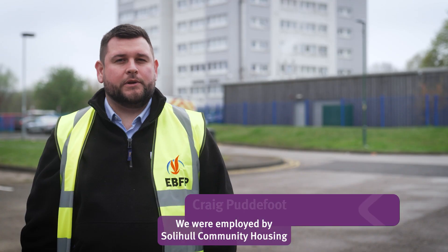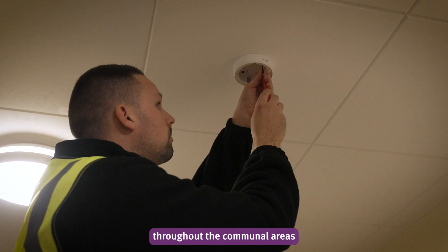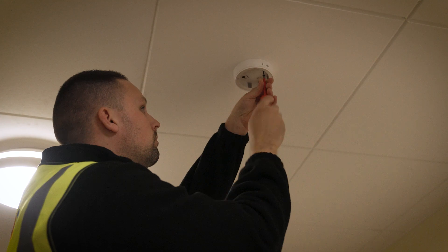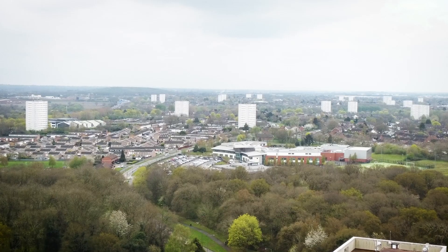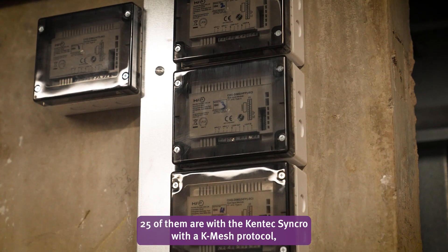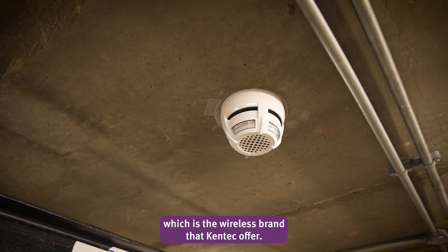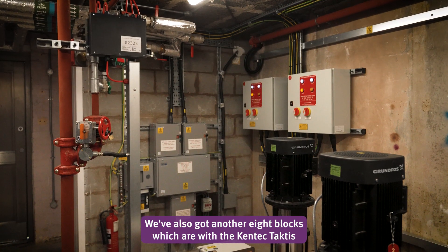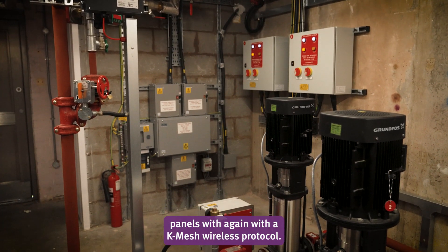We were employed by Solihull Community Housing to install fire alarm systems throughout the communal areas and in some blocks the actual residence areas. We were employed to do 33 blocks in total — 25 of them with the Kentec Syncro with a K-Mesh protocol, which is the wireless brand that Kentec offer, and another eight blocks with the Kentec Taktis panels, again with the K-Mesh wireless protocol.